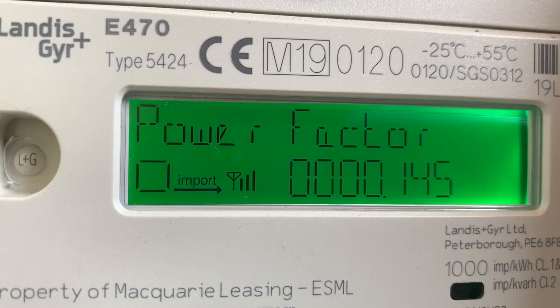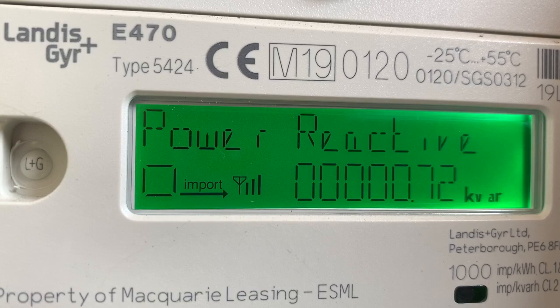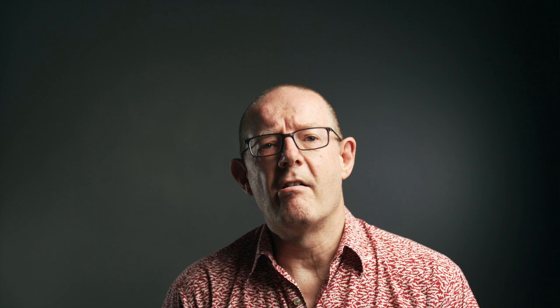As you can see here in this video, my power factor is very, very low — the values keep fluctuating as the load on the house changes. This was filmed at 4:30pm on a Thursday; the house load was about 1.9 kilowatts, one kilowatt was being supplied by solar, and the balance supplied by the Powerwall — there was no pull from the grid. Mike has pulled the Powerwall API data and has seen reactive power import and export figures shown in that data, constantly changing minute by minute. As you can see, power factor and reactive power are linked — we need to strive for a power factor of 1, which results in less reactive power.